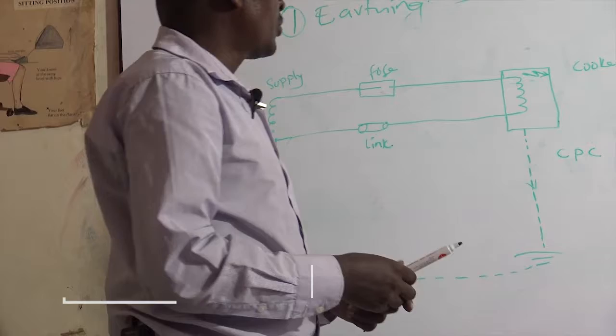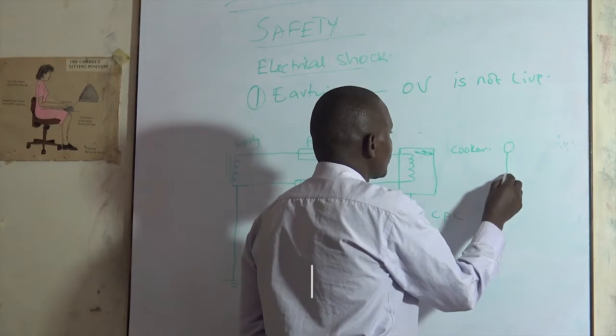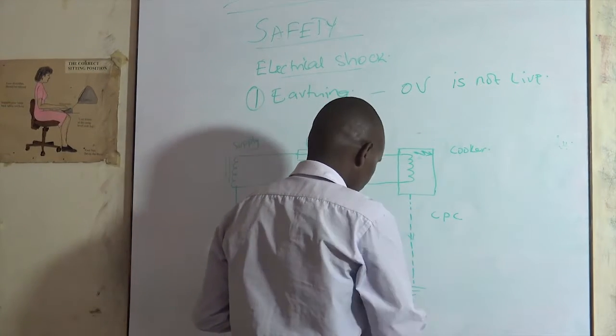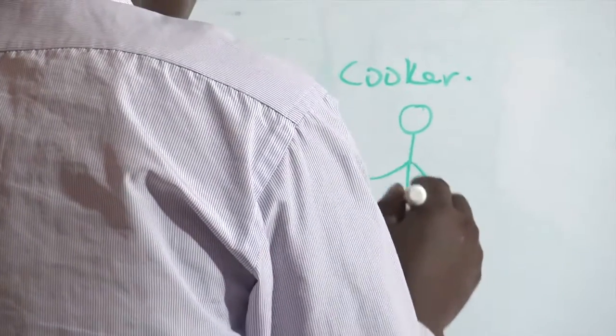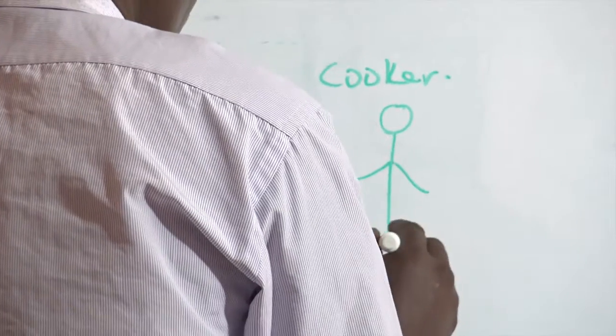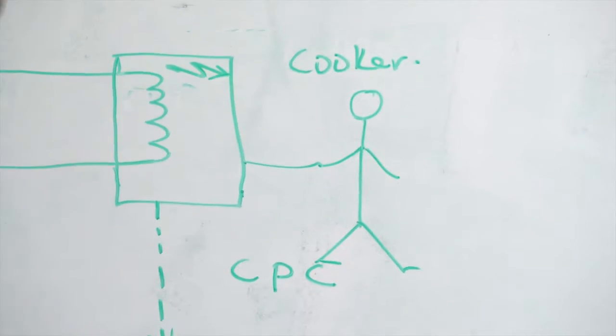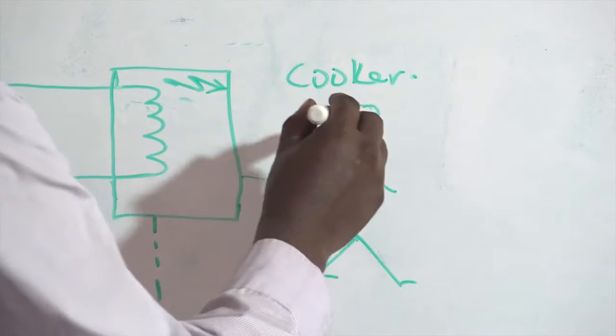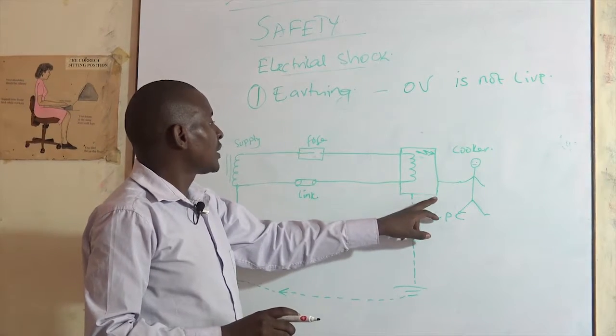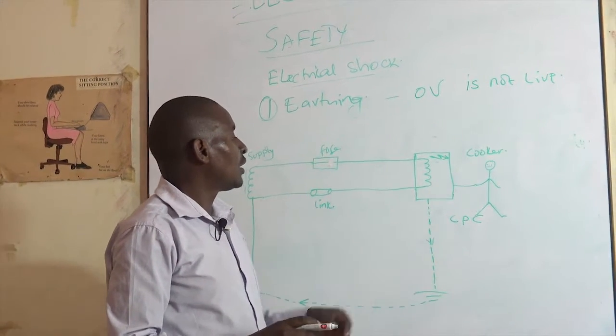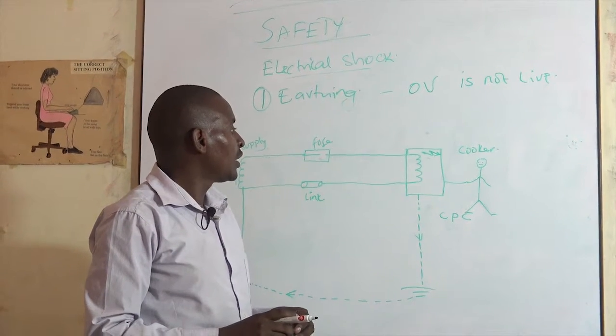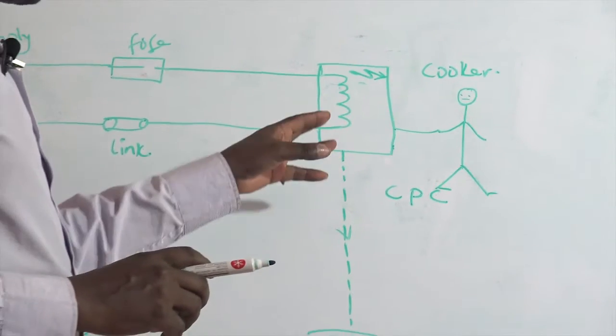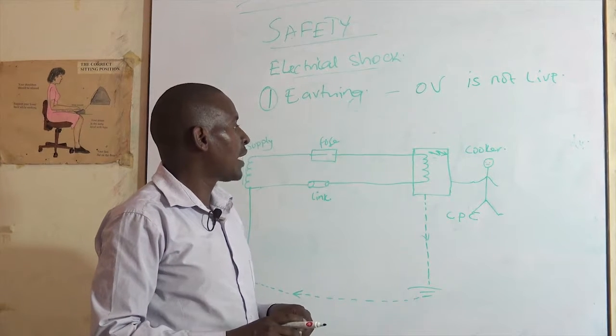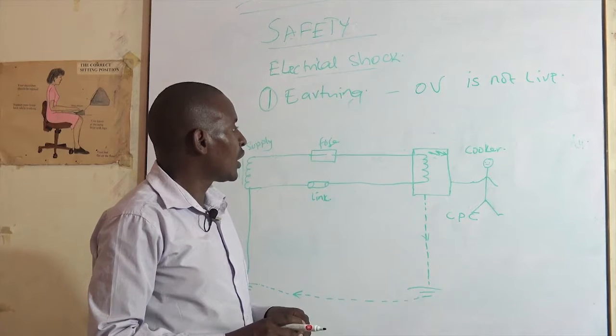And even if someone touches here, they cannot get an electric shock, simply because the potential of this metallic part is always at zero potential. So they are not at any risk of touching a live conductor. And within a very short time, the fuse or the circuit breaker will operate and isolate the faulty part, and by that the person who is using the cooker remains very safe.